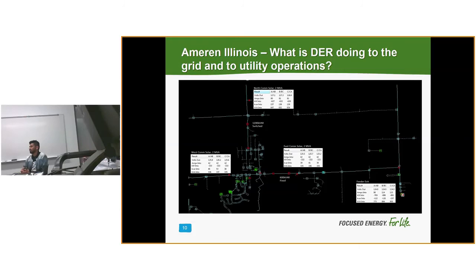So at a certain time of day, or a certain temperature point, I want it to come on, say at 9 a.m., or if the temperature reaches 72 degrees, for example. These are just some of the global parameters we put in our cap banks. So that could be why this switched cap bank was on. If I open it, I'm eliminating some VAR flow that could help bring that voltage down. How much? I don't know, but that would be one step towards solving the problem.